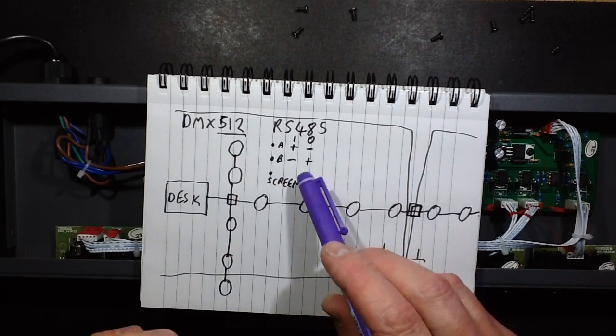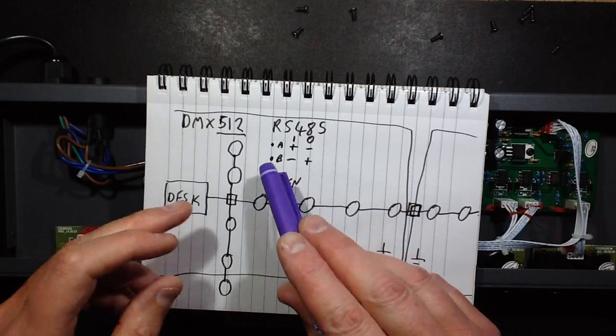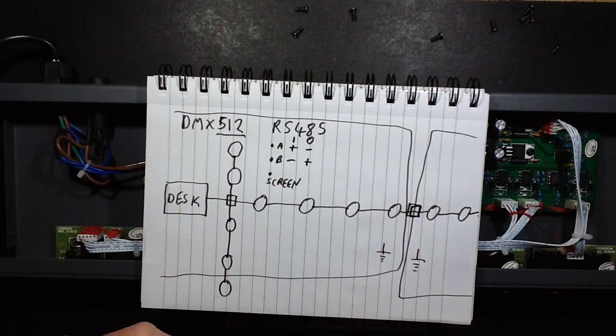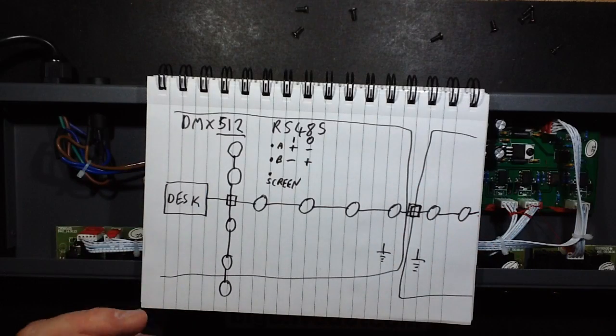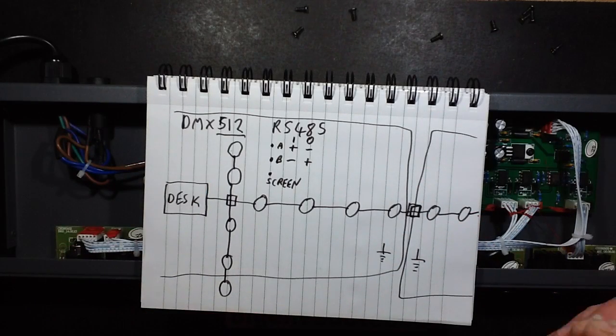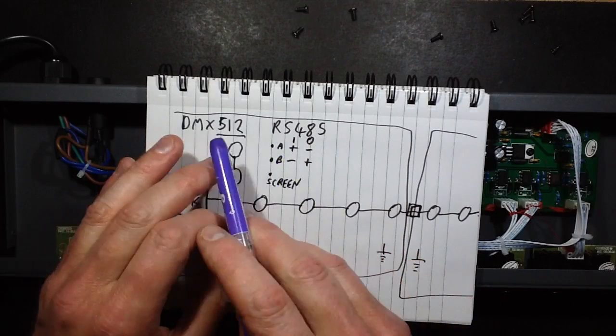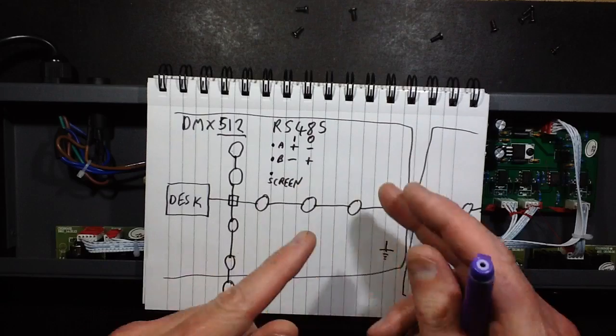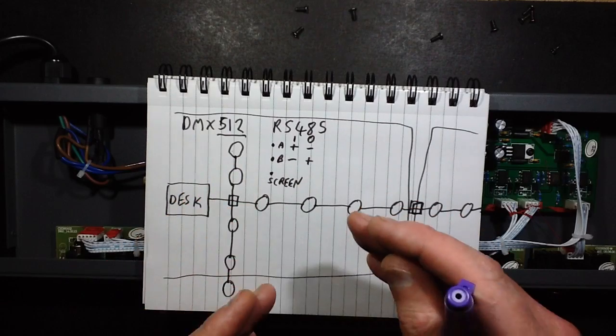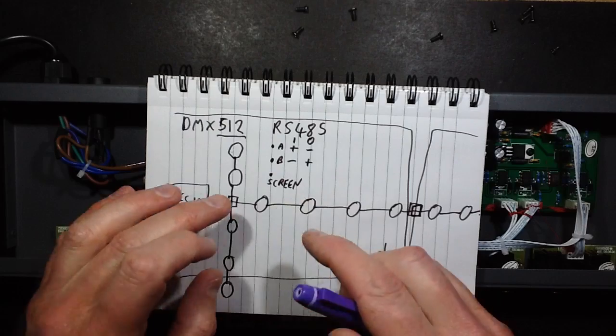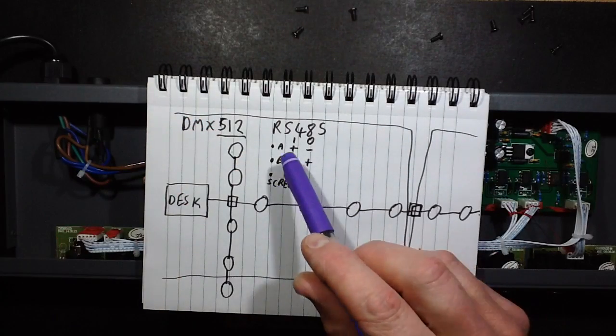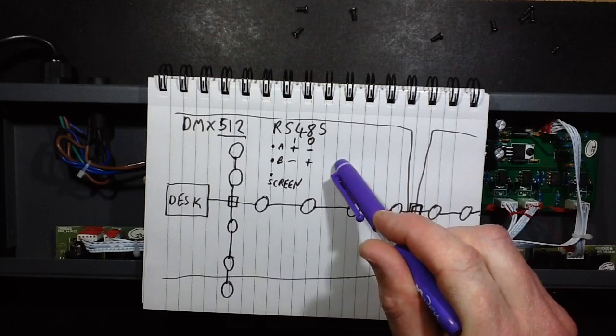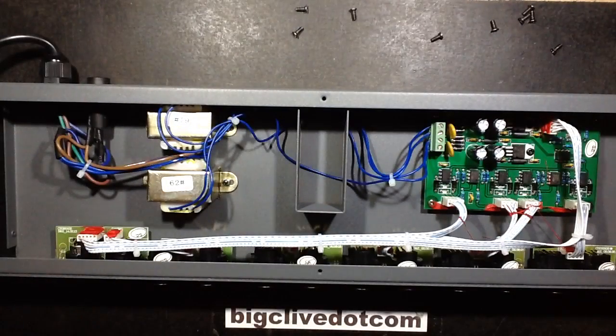It's also because it's a differential protocol. If there's any electrical interference induced onto the cable through running past high power cables, because it's inducing it onto both the A and B simultaneously as it passes, because the receiver chip only looks for the polarity difference between those two pins within a modest range from the screen level, it can reject common mode interference. So it's a very good robust standard.